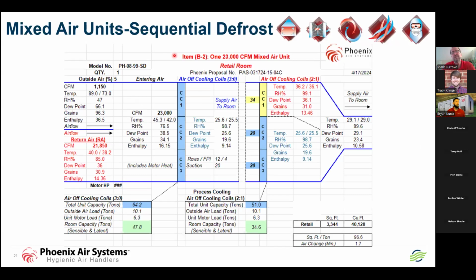We talked before about the 50-degree room temperatures. That's kind of a USDA mandate. If you're above that, you're going to have to go through something called the mid-shift cleanup. The colder we can keep the room, the more it's going to retard the growth of bacteria. So a lot of process areas now want to run at 40, maybe 36 degrees. We talked before about a 12-row, 6 fins per inch coil for a wet coil. This is something that we'll call a sequential defrost, where we are going to intentionally hit this with a 20-degree suction.